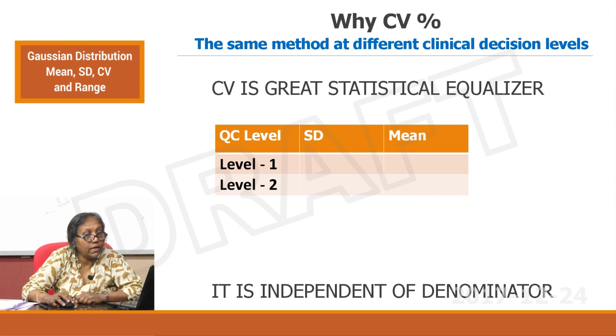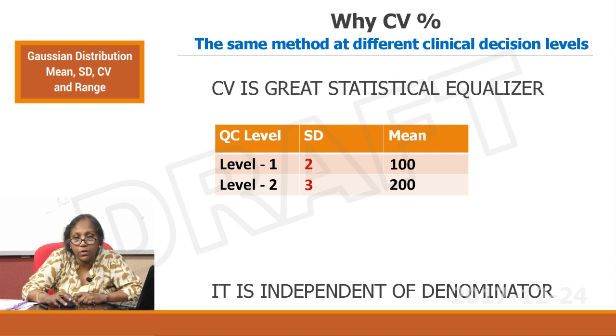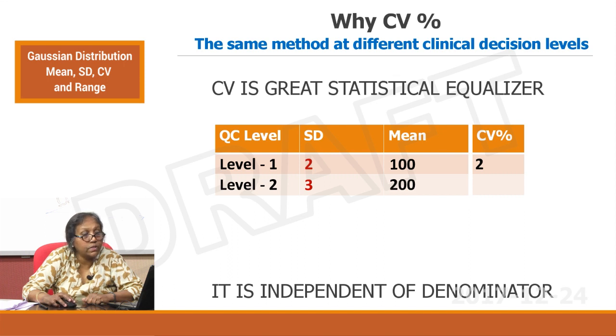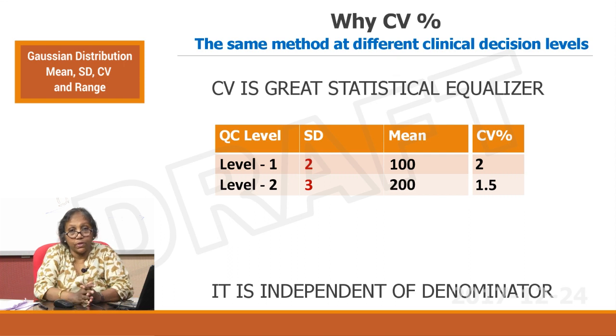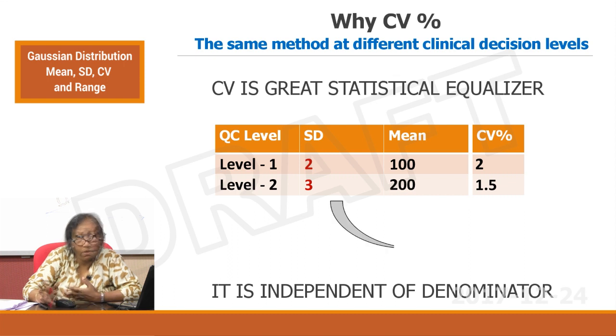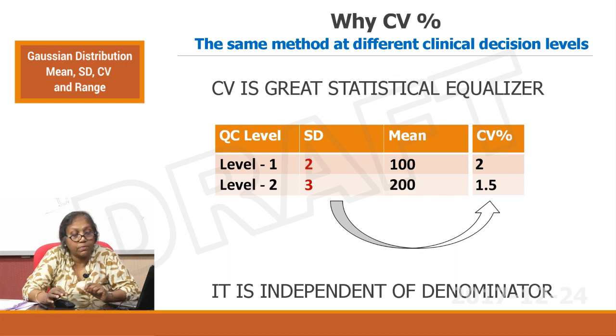Another example: two QCs — Level 1 with SD=2 and mean=100, and Level 2 with SD=3 and mean=200. Looking at SD alone you might think Level 2 has more dispersion. But calculating CVs: Level 1 CV = 2/100 × 100 = 2%, Level 2 CV = 3/200 × 100 = 1.5%. The CV is actually better in Level 2 though the SD is higher, because the mean is also higher. If you did not calculate CV%, you would not be able to understand which is the better performing level.